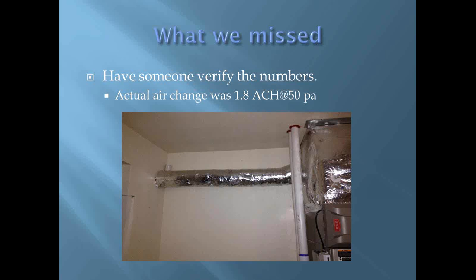One of the mistakes I made is I have a really deep crawl space. It's 3 feet to the bottom of the trusses. And it has a transfer grill and a ventilator, so it's considered the same volume as the house. It's conditioned, it's tempered, and I didn't calculate that space in there. If I add that space in there, it brought me down to 1.8.